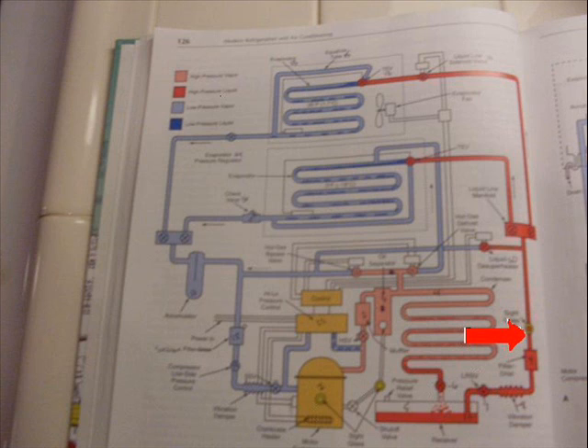The sight glass will also show bubbles in the system after it's been running for a few minutes. If we see bubbles or the sight glass only appears partially full, it's an indication that we may be undercharged, not have enough refrigerant in the system. It is possible sometimes to detect non-condensable gases in a system because you will have bubbles go through the sight glass. Your pressures will be higher than normal on the high side because you cannot condense the gas. And so you can see bubbles in the sight glass and those bubbles could be non-condensable gases. That's why I say it could be low on charge. Overwhelmingly, that's true. You might occasionally run in a system where the bubbles were created by non-condensable gases. Air, a different refrigerant that's used in the system. Somebody screwed up and left nitrogen in it, left CO2 in it when they were purging.